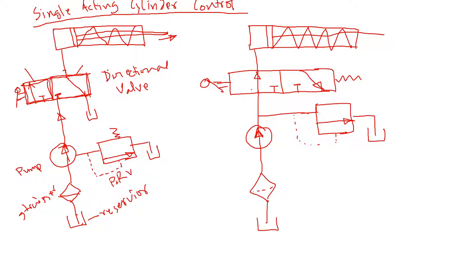When we engage the left manually-controlled lever, we engage that envelope. This one was a forward slash and this one is a backward slash. When you engage this envelope, you can see the pump line — wherever the flow is coming from — is connected to this line. You can think of it as sliding that whole piece to the right so the left envelope gets engaged.